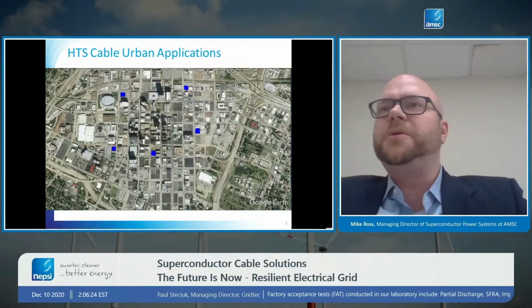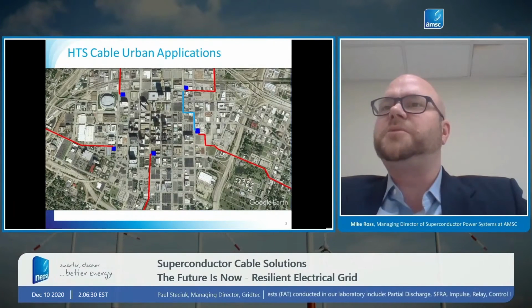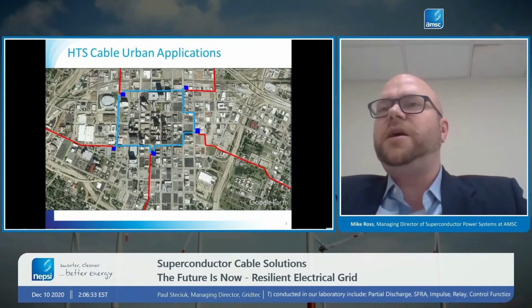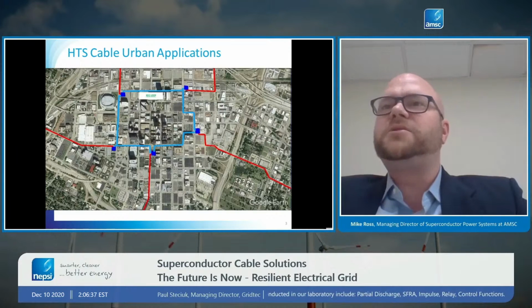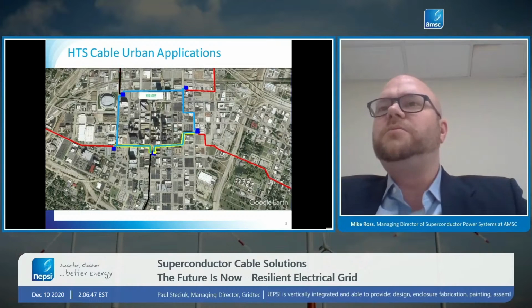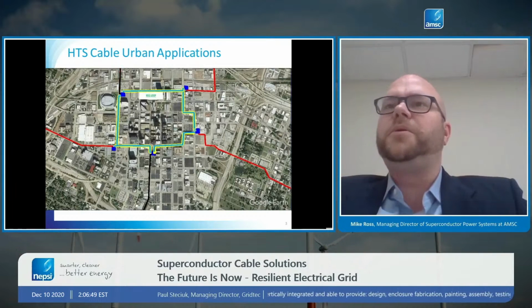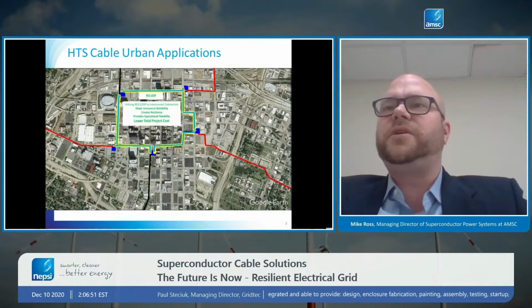There's some reliability and redundancy built into the transmission grid, but there's no interconnections between substations at the distribution level. So if you do have an outage to any substation, you have a blackout. So one of the main applications of superconductor cables is to loop the substations together at the distribution side, so that if you do have transmission outages, you can move power around the urban area in these very, very high capacity cables that we'll talk about in more detail here shortly.